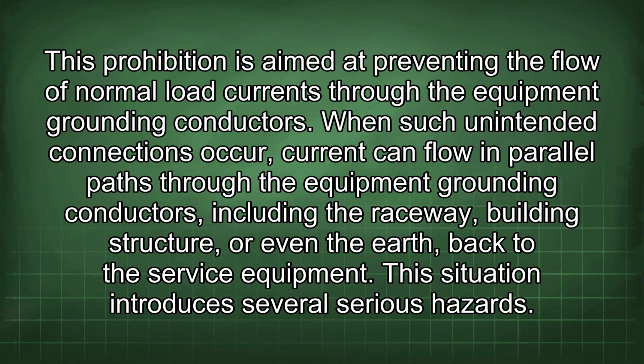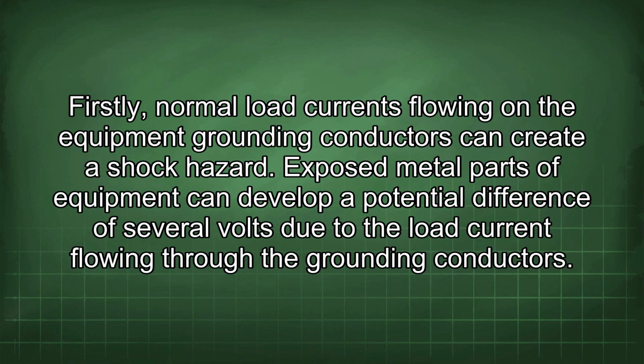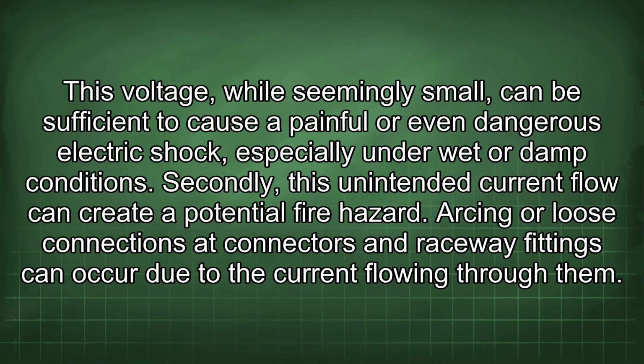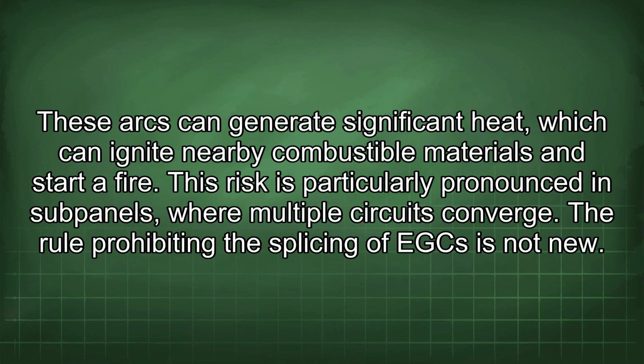This situation introduces several serious hazards. Firstly, normal load currents flowing on the equipment grounding conductors can create a shock hazard. Exposed metal parts of equipment can develop a potential difference of several volts due to the load current flowing through the grounding conductors. This voltage, while seemingly small, can be sufficient to cause a painful or even dangerous electric shock, especially under wet or damp conditions. Secondly, this unintended current flow can create a potential fire hazard. Arcing or loose connections at connectors and raceway fittings can occur due to the current flowing through them. These arcs can generate significant heat, which can ignite nearby combustible materials and start a fire. This risk is particularly pronounced in subpanels, where multiple circuits converge.